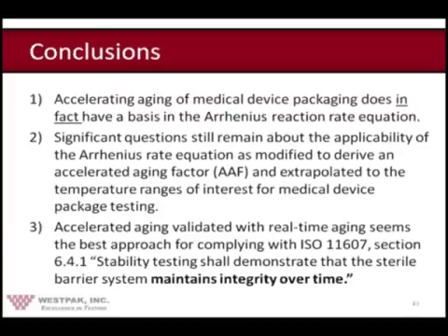Finally, that accelerated aging validated with real-time aging is the best approach for complying with the ISO 11607 requirement of stability testing that demonstrates a sterile barrier system that maintains integrity over time. So the underline over time, that's the important thing. Okay, that's what we're really trying to do, and that's what the accelerated and real-time aging does for us.